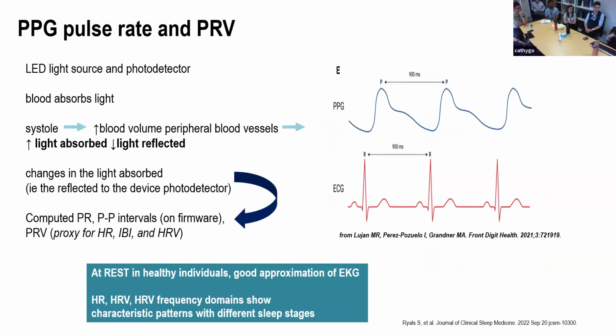And then there's also a photodetector. The reason this is on your watch is because blood absorbs light. After systole, the peripheral blood vessels are going to fill with blood, so your blood volume is going to go up. There's going to be increased light absorbed and decreased light reflected back to the photodetector. Those changes in light absorbed versus light going back to the photodetector allow this device to measure photoplethysmography, from which pulse rate, P-to-P intervals, and pulse rate variability are calculated.